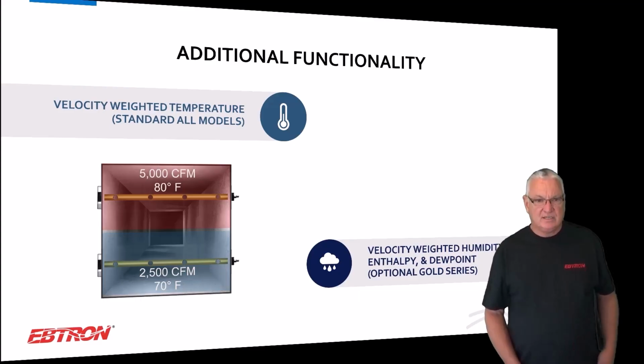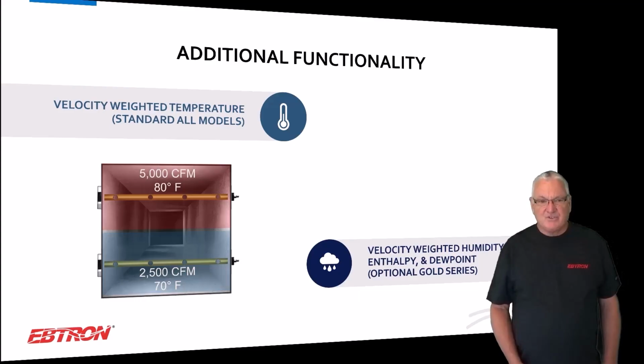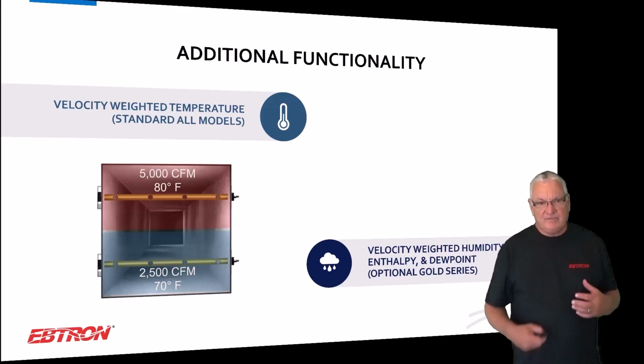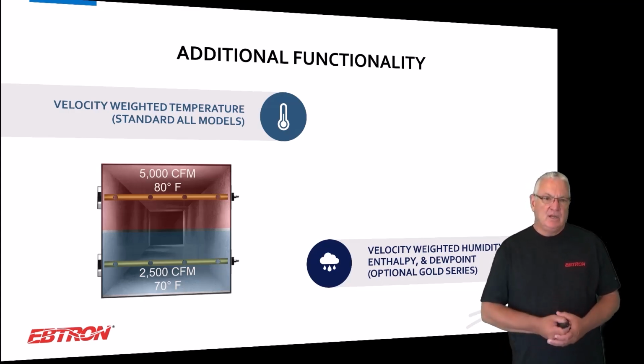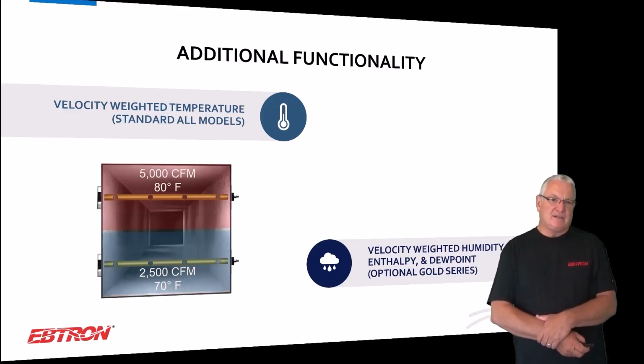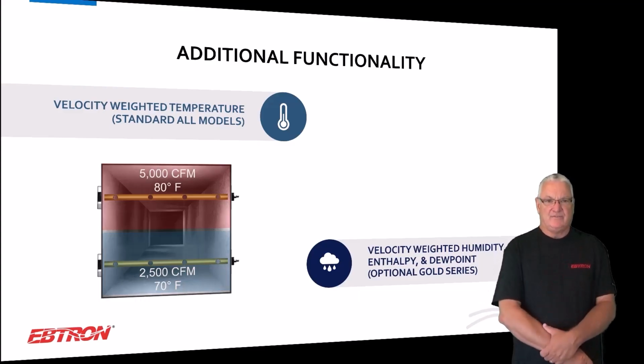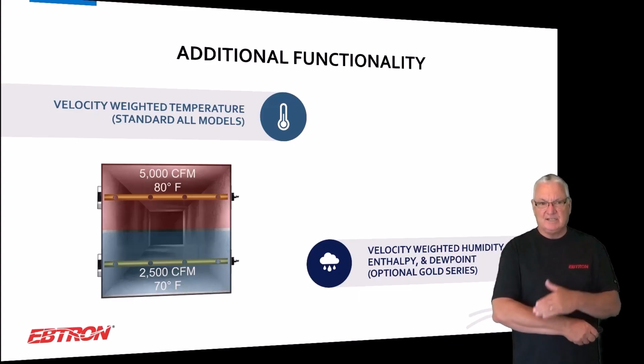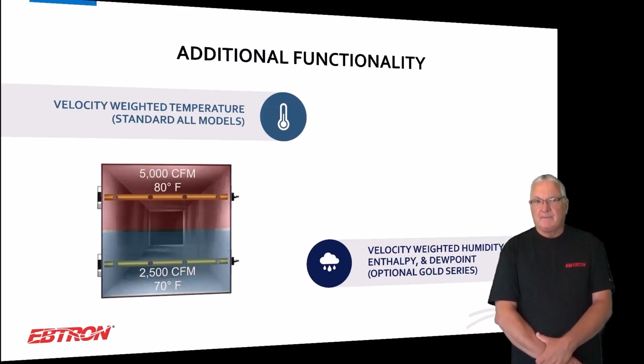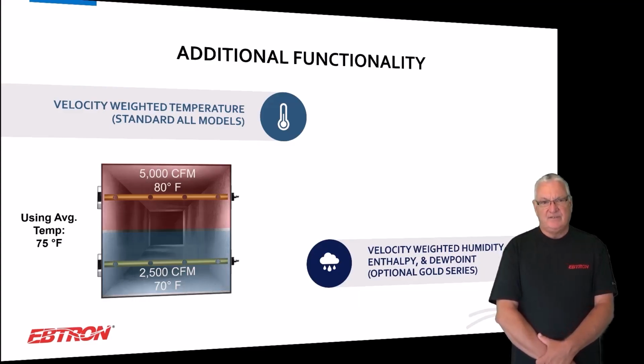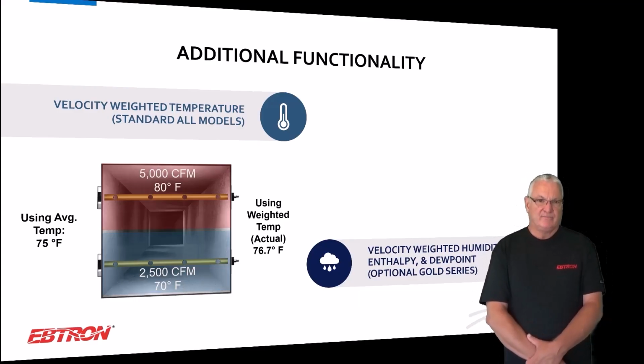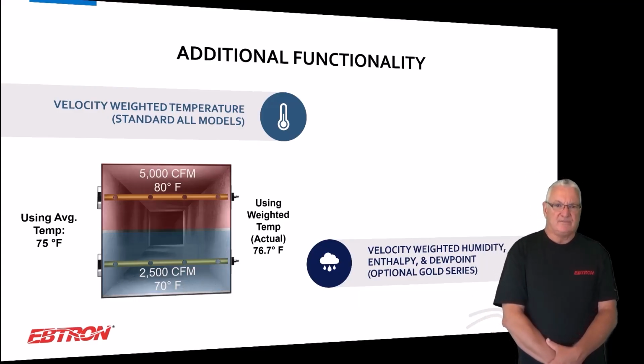What's the difference? Okay, well, a lot of times when you're doing these measurements, you're measuring at a point or a couple points, but you're not recognizing the fact that when you have a velocity profile, you have to weight the temperature. So just look at this very simple example. The top of the duct is 5,000 CFM, the bottom of the duct is 2,500 CFM. The top of the duct is 80 degrees, the bottom of the duct is 70 degrees. What's the temperature of that airstream? It's not 75. It's twice as much air at 80. It's 76.7.